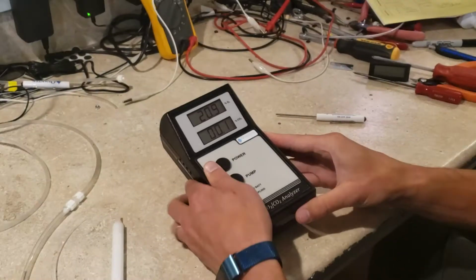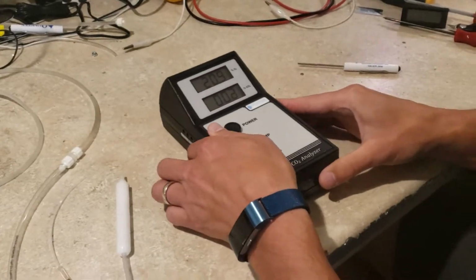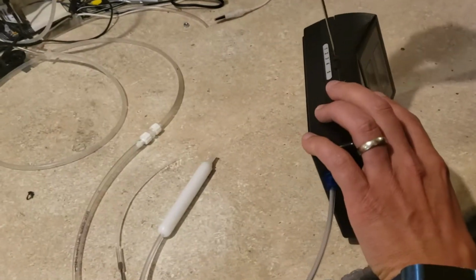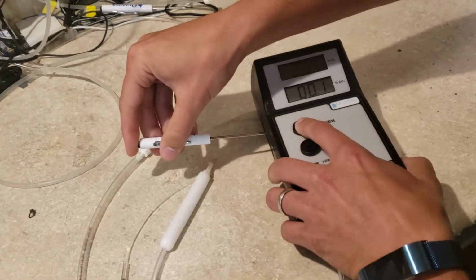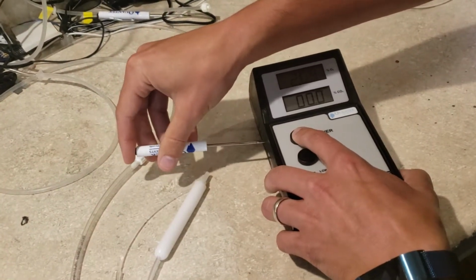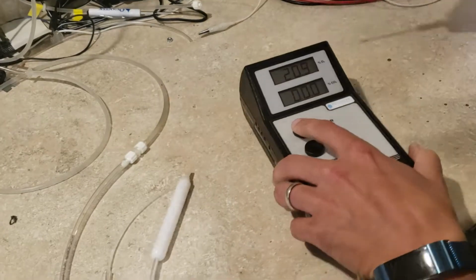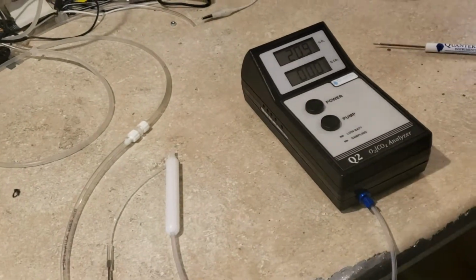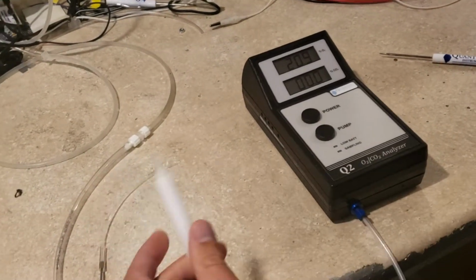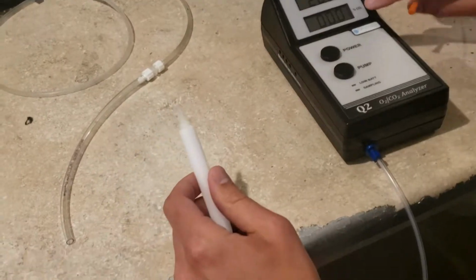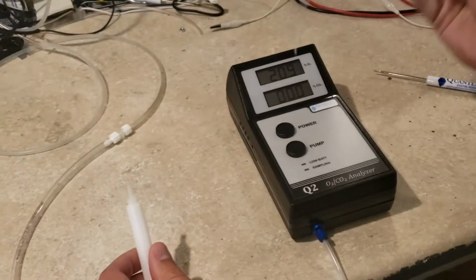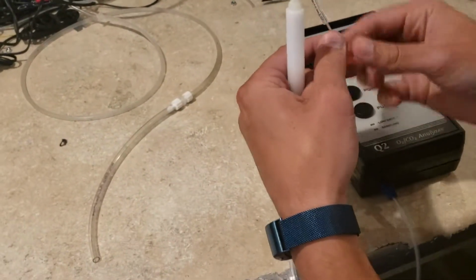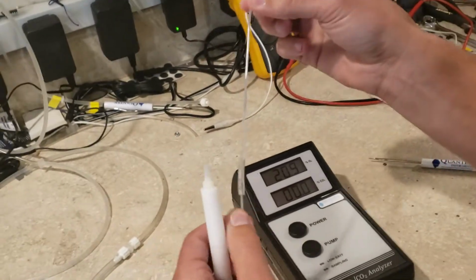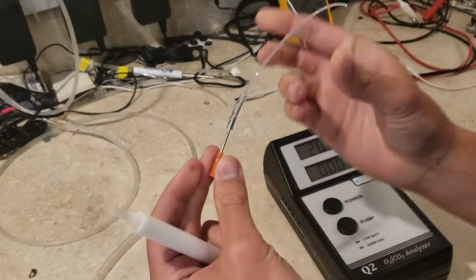So now we have it set at 20.9, 0.1, and we're going to go ahead and perform a calibration for the CO2. I'm just fine-tuning the 0 here a little bit. There we go. Perfect. Okay, so we're at 20.9, 0.0. The next thing we want to do is calibrate the CO2. To do this, we're going to use a calibration tube, which is just a blunt needle with some tubing connected to it. It's about 4 inches long.